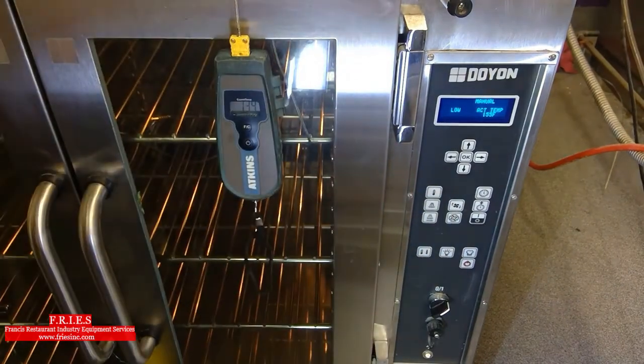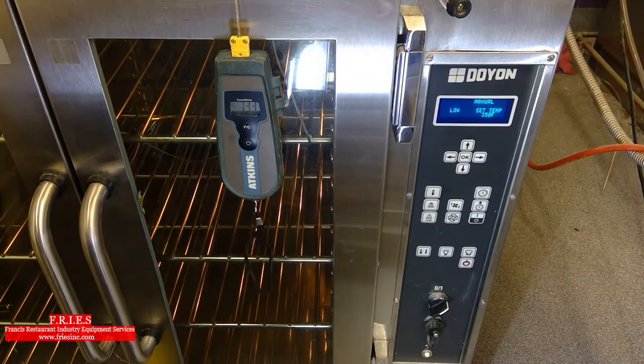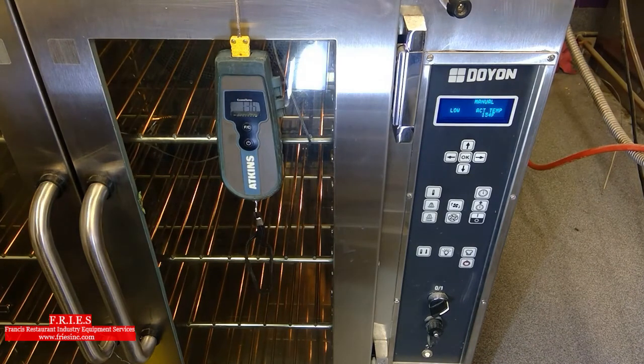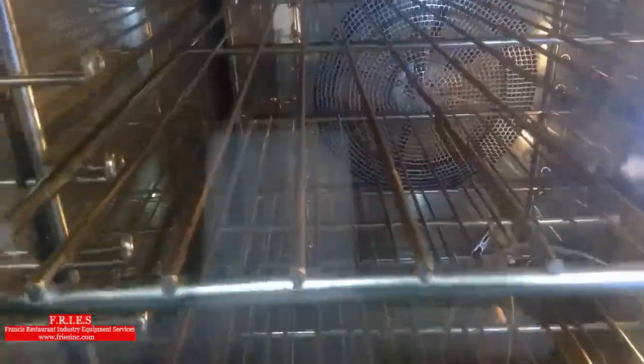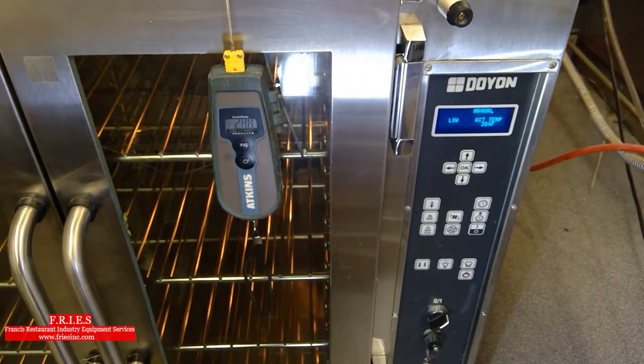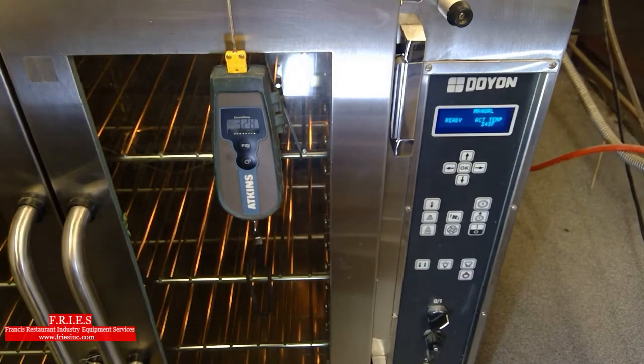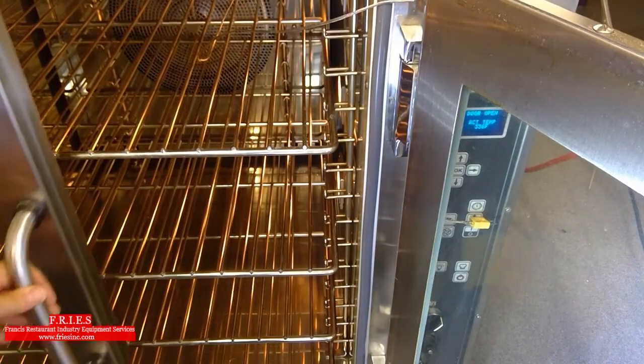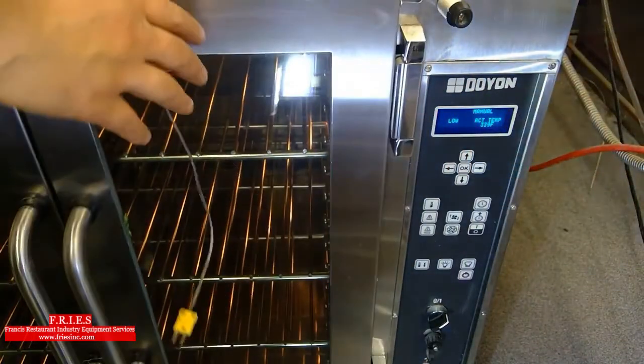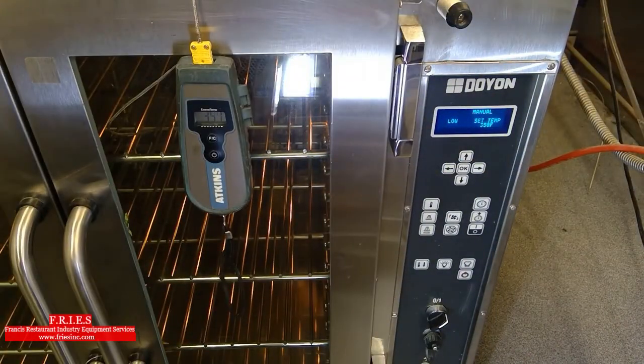Alright, so I'm just going to fire up the oven here. Alright, it's heating up. I'm just going to hit fast forward here. And we just want to make sure we hit our set point. So temperature's off by about 20 degrees. I'm going to move the probe closer to where the sensing bulb is. And let's see how much closer we can get if we need any adjustment or calibration. So we're cycling off. So you can see we're at about 353. And the screen's showing about 350. We're off by 3 degrees. 3-4 degrees. I'm good with that. We're within the range.